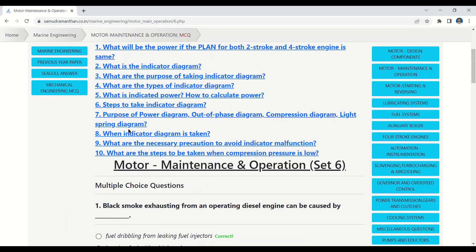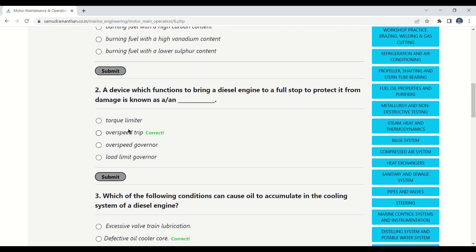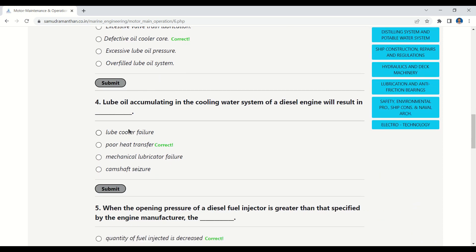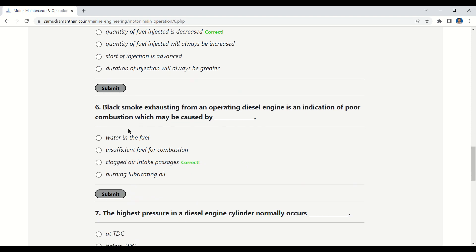Let's revise what we covered in this video: Black smoke from a diesel engine can be caused by fuel dribbling from leaking fuel injectors. The device to bring a diesel engine to a full stop is an overspeed trip. Oil accumulates in the cooling system due to a defective oil cooler core. Lube oil in the cooling water system results in poor heat transfer. Greater-than-specified injector opening pressure means the quantity of fuel injected is decreased. Black smoke indicating poor combustion may be caused by clogged air intake passages.